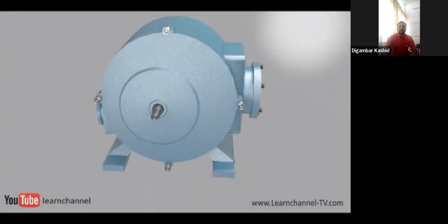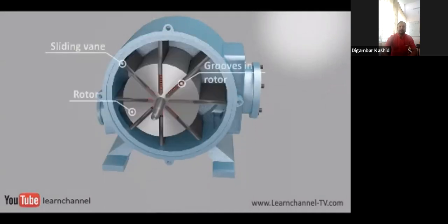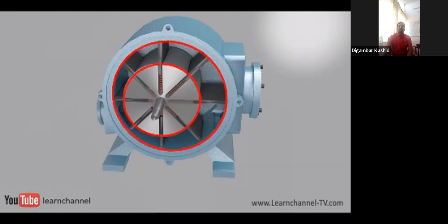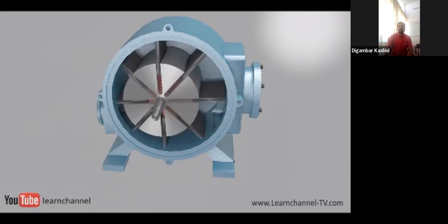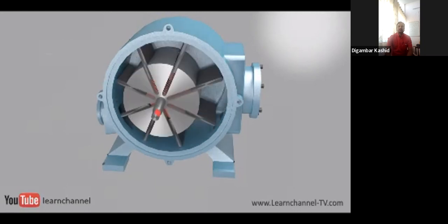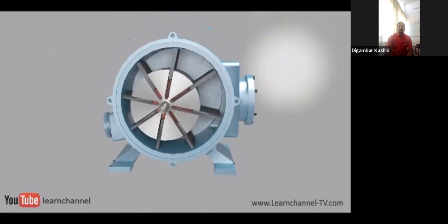A totally different working principle has the so-called rotary compressor, also named as vane compressor. A rotary compressor has a cylindrical housing. Adjustable rotary vanes with their center point on an offset drive shaft have contact with the housing. So when the shaft rotates, these vanes create chambers of variable sizes. Air is sucked into the largest chamber, compressed, and leaves the compressor at the smallest chamber.